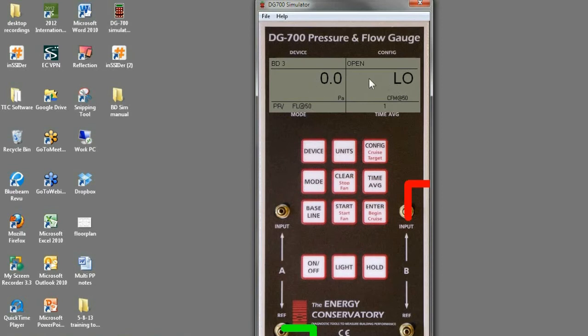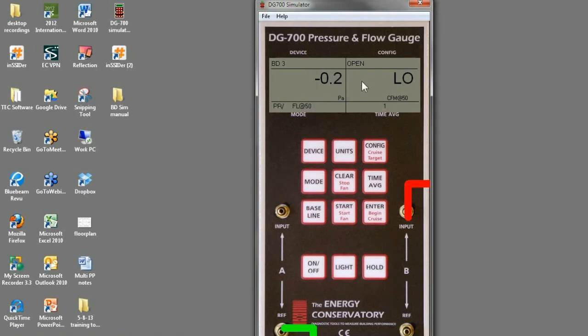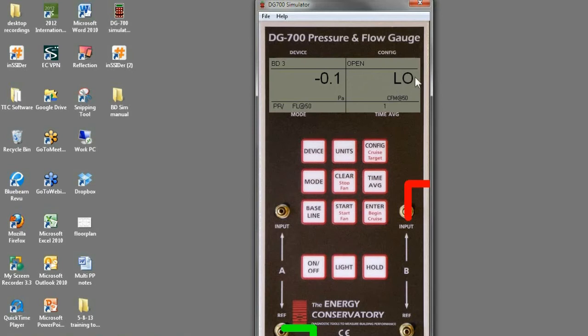Channel B, instead of reading the flow through the fan as it would with the pressure flow mode, it's not reading the flow through the fan. What it's reading is what the flow would be if it were at 50 pascals. So once we get over 10 pascals, it'll alternate between low and a number. When it gets up high enough, it'll just display just a solid number here, which is the flow adjusted for what the flow would be if you were at exactly 50 pascals. So that's pressure flow mode.